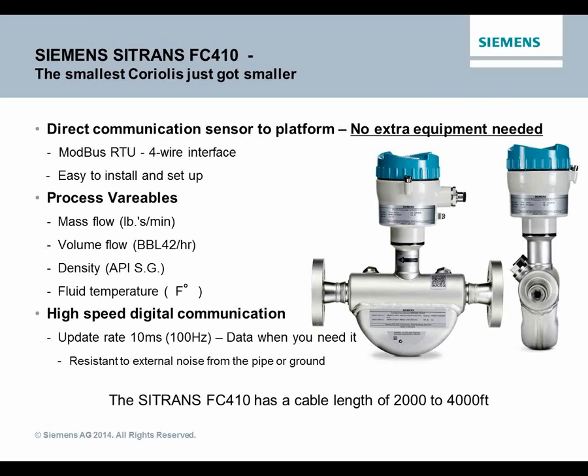The driving frequency is dependent because what the meter is trying to do is drive the frequency of the tube to its resonant frequency, the frequency with which the tube naturally wants to vibrate at. Everything has a resonant frequency. Every vibratory structure does. Now, a tube filled with air has a different resonant frequency than a tube filled with water. And a tube filled with water will have a different resonant frequency than one filled with, say, liquid mercury. I just keep picking that because that's one of the denser fluids I'm aware of.